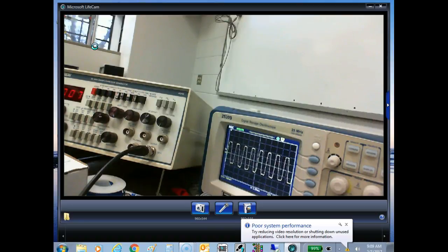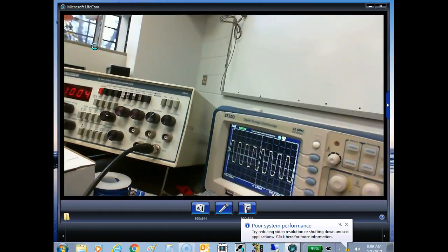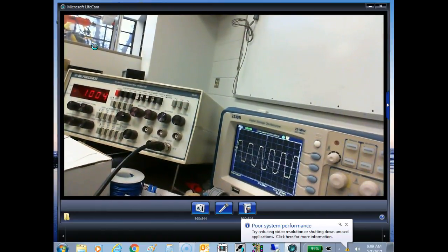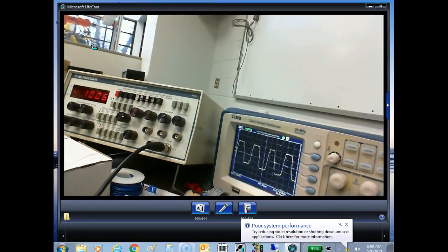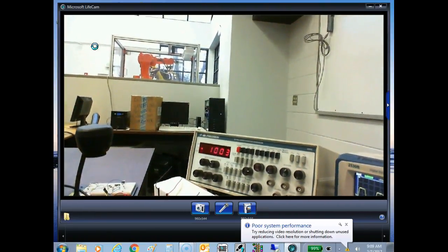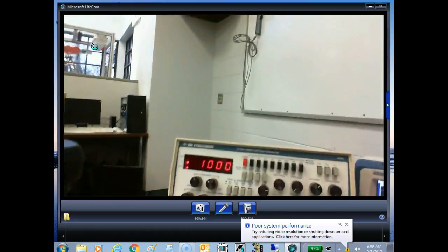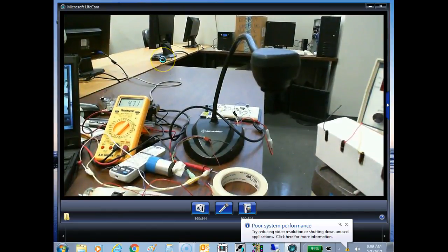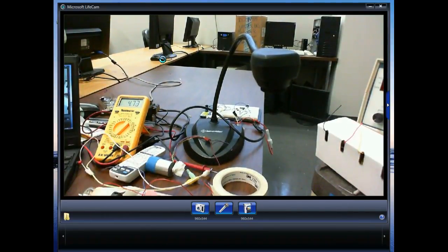So when we speed up the motor, it speeds up the tach generator. The tach generator outputs voltage that is proportional to speed. You can see here's my meter right here, and I'll change the speed of the motor. When I slow the motor down, what happens to the output voltage of the tach generator? Yeah, it decreases. And all we're doing on a DC motor, of course, is changing the voltage on the armature. So right now we're getting 4.75 volts in the motor.